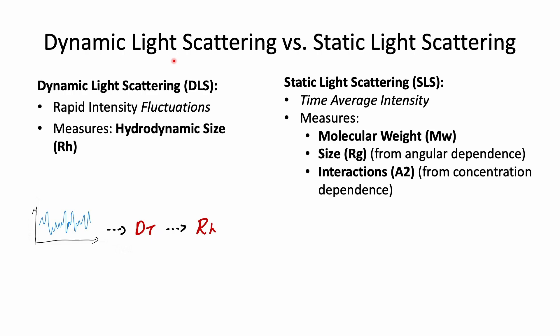There are two main types of light scattering techniques: dynamic light scattering and static light scattering. We have covered dynamic light scattering in another video — please check that out if you're interested. The focus of today's show is static light scattering. It is 'static' because, as opposed to dynamic light scattering, the SLS technique is interested in the time-average intensity of the scattered light. Instead of analyzing fluctuations, we measure the total scattered light at different angles and often at various sample concentrations.